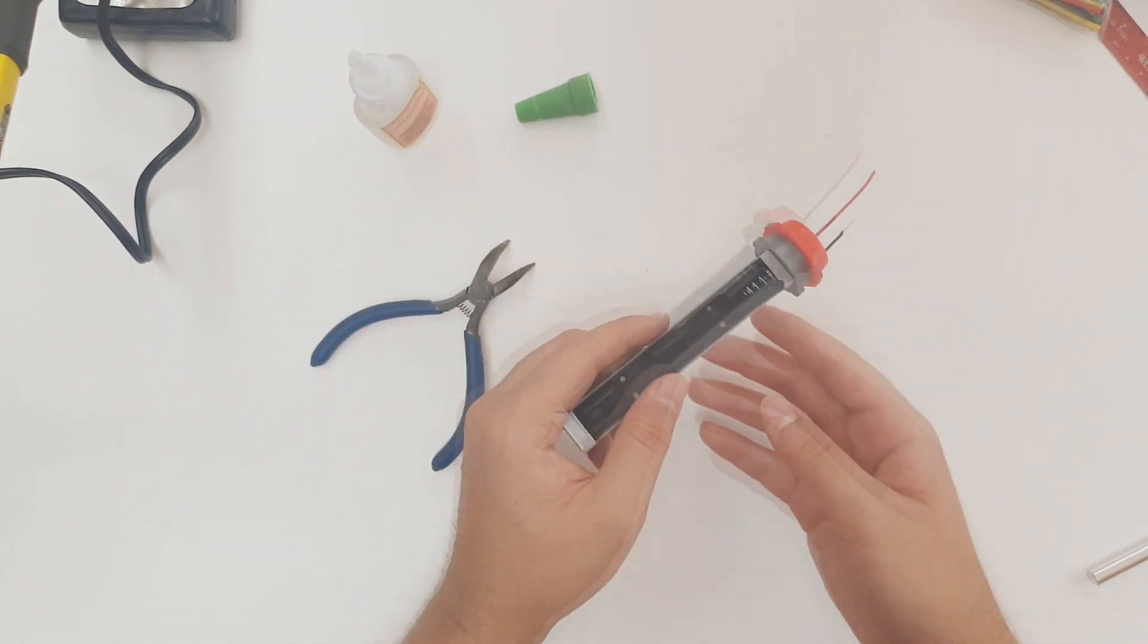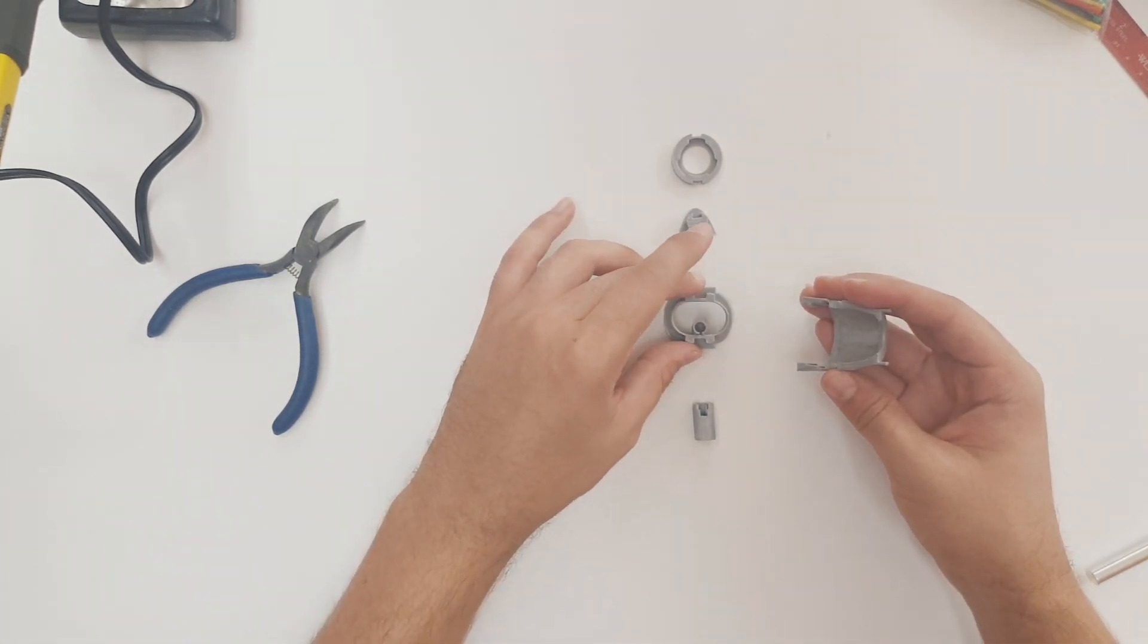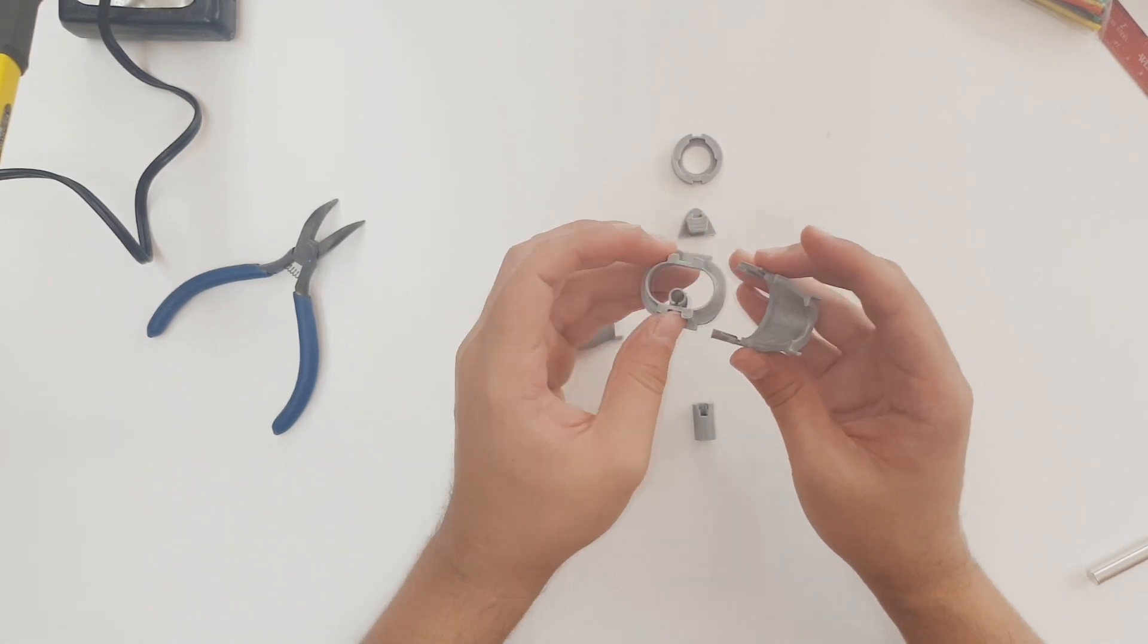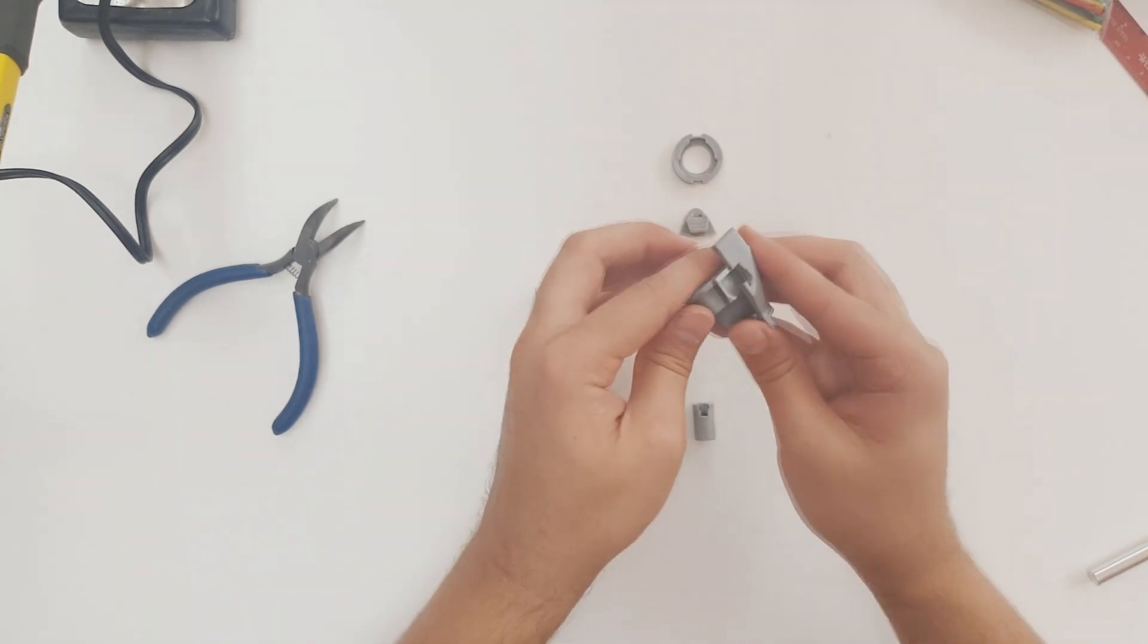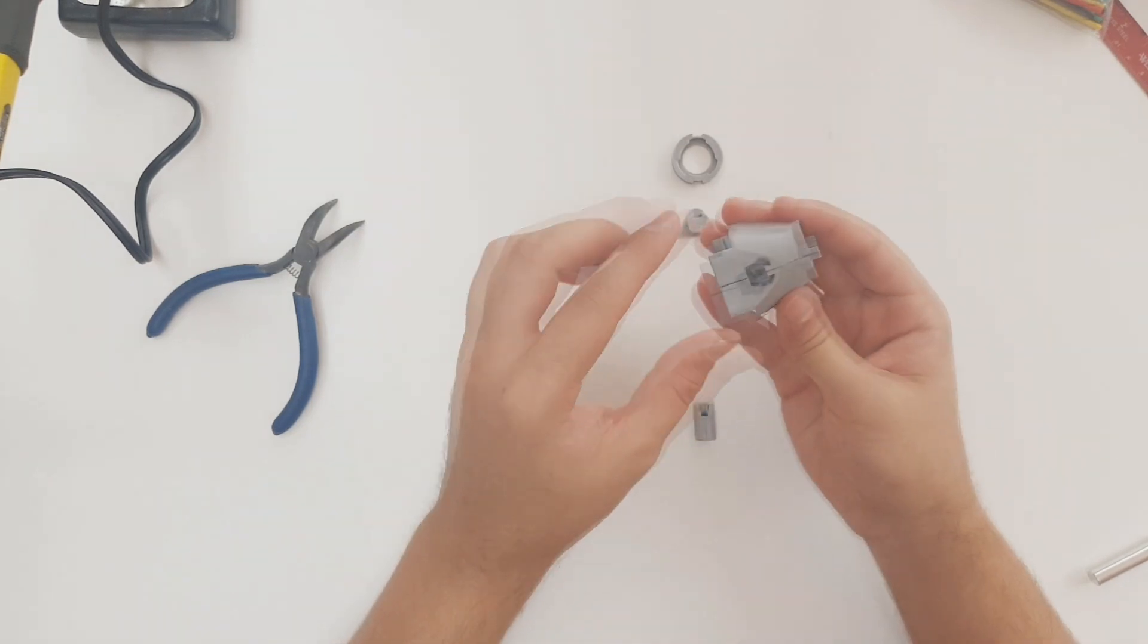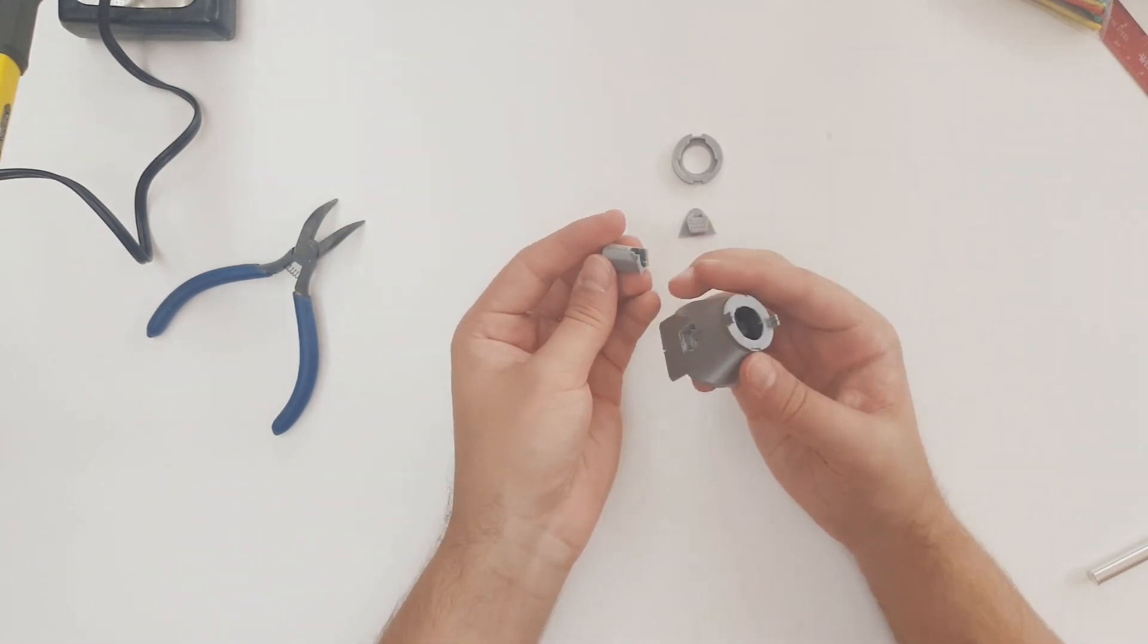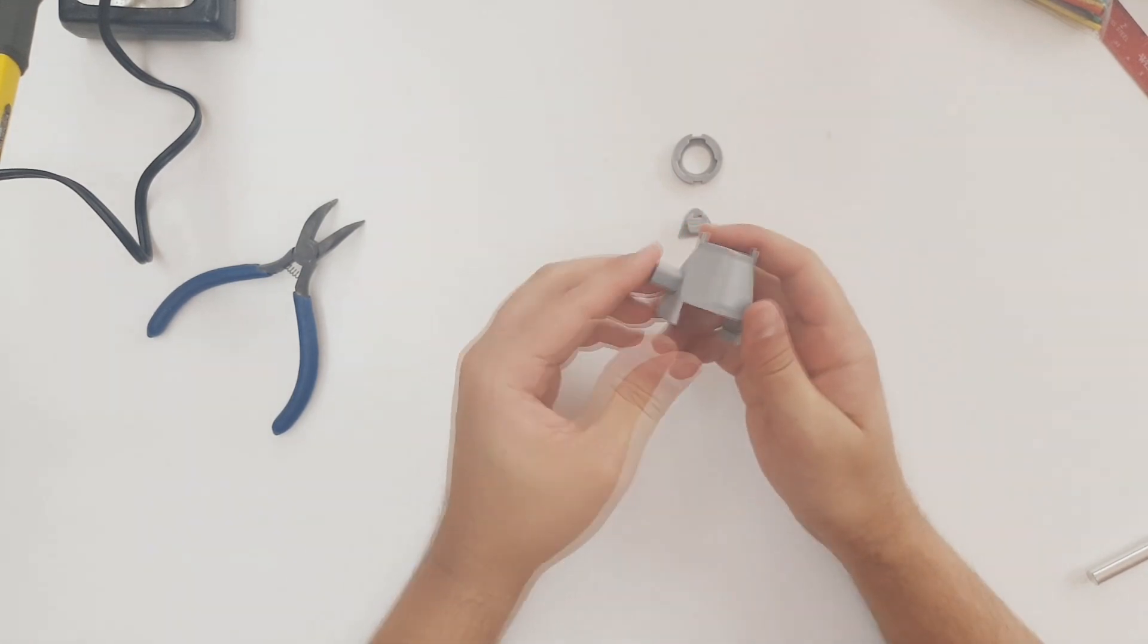We'll set that aside and start working on the otoscope head. The otoscope head fits together like so. One of the head halves is connected to the inner head part through these top and bottom rails on the inner head. Once that's secure, the other head half is connected. On the bottom of the head, there's a hole for access to the LED area, and this is where the neck part gets pushed into. It should clip into place.